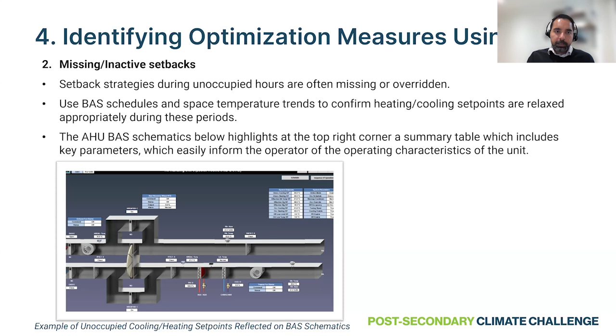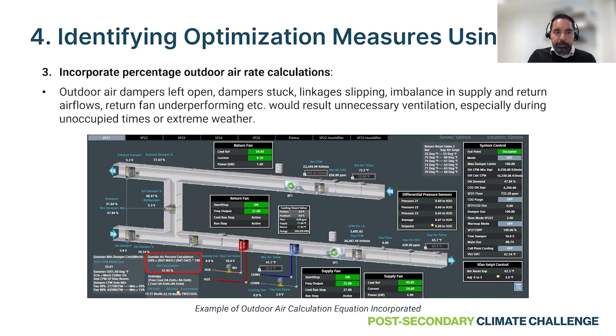where on the graphics itself, this formula was added to identify what outside air percentage this system is currently bringing in. In this case, I think it is economizer mode, if I'm not wrong, and the system was running at 57%, which is fine. But you will see in some cases during the winter time, if this graphic and this calculation exist on your building automation system, you will notice in the middle of the winter if the outside air percentage is higher than what you would need for this system, you could easily identify that with just one graphic with this percentage, and then you can engage your team to fix that issue. So having this information readily available to you and your team will help you identify and implement these measures much more easily.